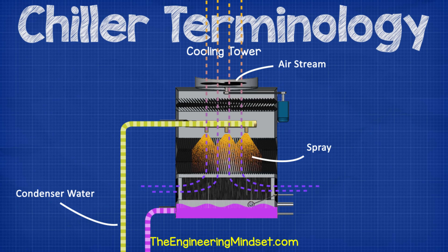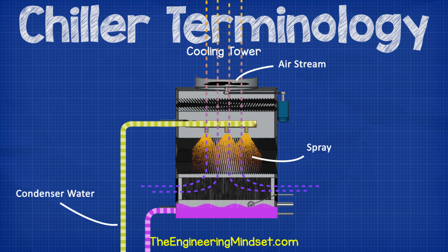Cooling tower, often referred to simply as just the tower. These sit on the outside of the building, usually on the roof, and are only used with water-cooled chillers. They will be either wet or dry type, but both types use fans to move air through the tower. With wet type, the condenser water circuit is open and the water is sprayed into the airstream, which removes the heat and cools the water down. In a dry type, the condenser circuit is closed and the water passes through a heat exchanger where the airstream blows across to remove the heat. Additionally, some cooling towers will spray water over the cooling coils to help remove the heat.